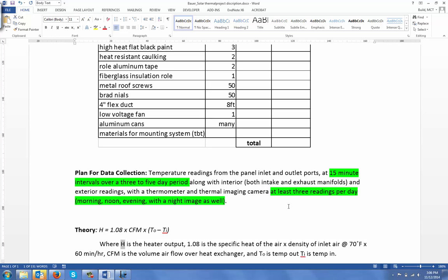Yeah, but it's a little more subtle than that, because if we got CFM, we're looking for power here, and enthalpy is just how much thermal energy is in a system. It's not how much is flowing through it, it's how much is inside it. So I want to be pretty clear on that. There's nothing wrong with your equation, it's fine, it just kind of gets down in the engineering weeds a little bit.